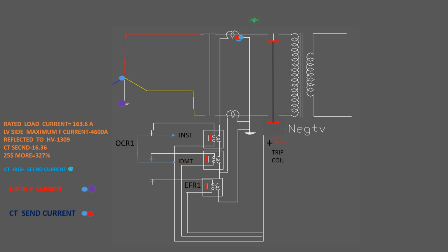But during any earth fault after the CT towards the power transformer winding, the source current will be divided into two return paths. One is through earth, where the earth fault occurred, and another through the power transformer winding. So here the source current is carrying two types of current. One goes to earth and one goes to the transformer winding. So this creates a difference current in the CTs. The CT secondary will take the difference current.